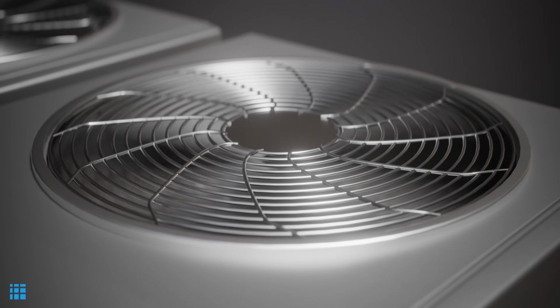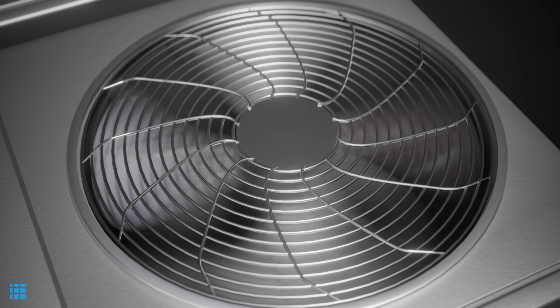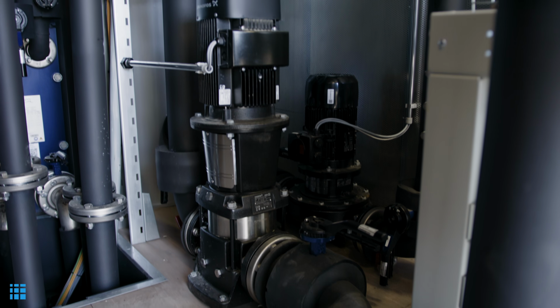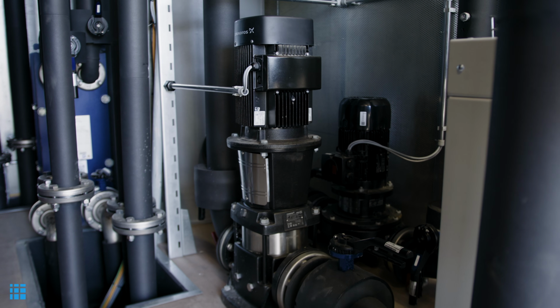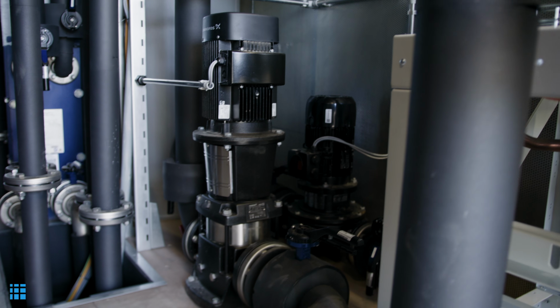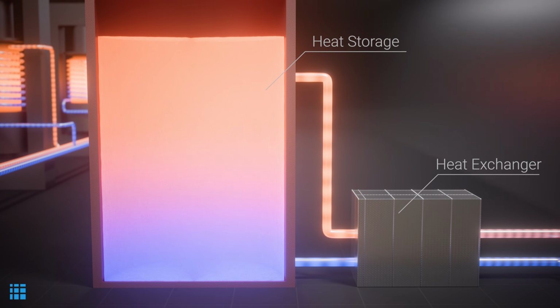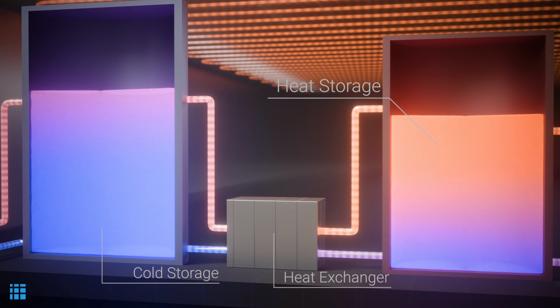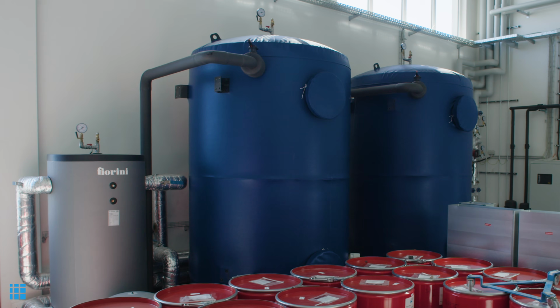The primary method of heat dissipation is air cooling supplemented with cold well water. If that is not sufficient, compression cooling automatically takes over. Additionally, 2 heat pumps are used to provide efficient heat exchange by further lowering the temperature of the coolant and storing the excess heat in storage tanks.